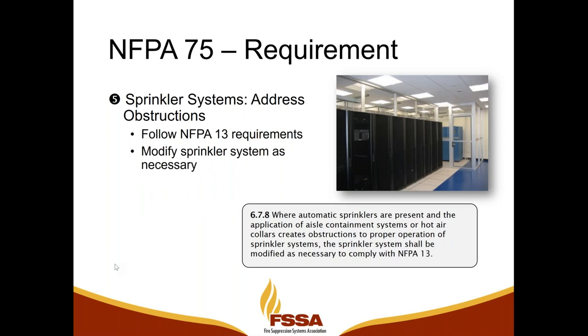Point five is for sprinkler systems. And so we'll touch on some sprinkler things and then some suppression things as we move towards our eighth requirement. The fifth requirement, sprinkler systems, we need to address obstructions. So with those new obstructions that get installed as part of the aisle containment system, we need to follow NFPA 13 requirements and modify the sprinkler system as necessary.